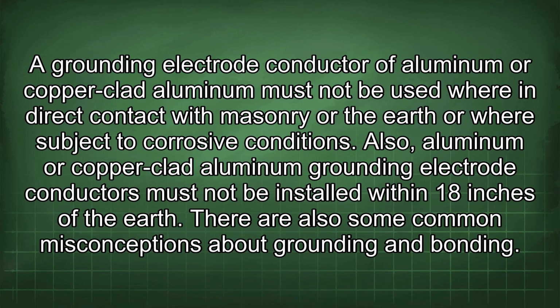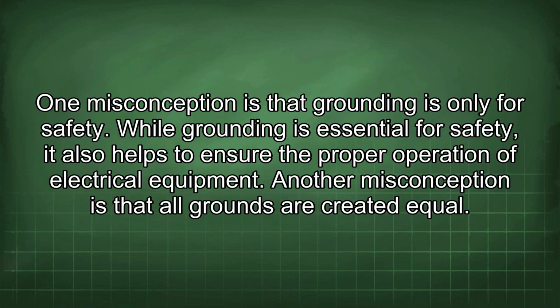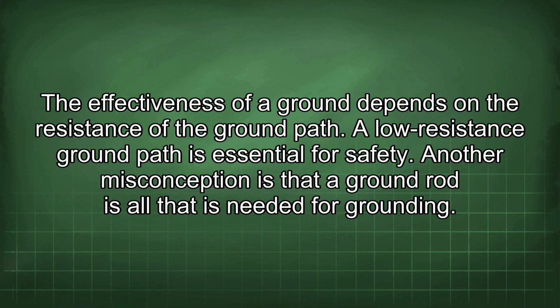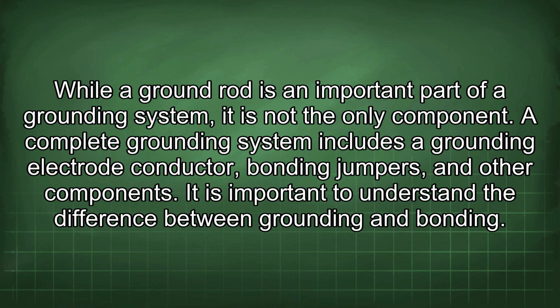There are also some common misconceptions about grounding and bonding. One misconception is that grounding is only for safety. While grounding is essential for safety, it also helps to ensure the proper operation of electrical equipment. Another misconception is that all grounds are created equal. The effectiveness of a ground depends on the resistance of the ground path. A low-resistance ground path is essential for safety. Another misconception is that a ground rod is all that is needed for grounding. While a ground rod is an important part of a grounding system, it is not the only component. A complete grounding system includes a grounding electrode conductor, bonding jumpers, and other components.